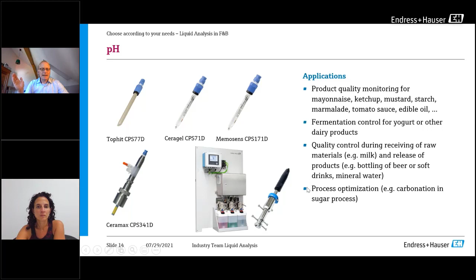Beside that, if you look at the lower left part, we have here an enamel part. To the right is what Floor introduced: a completely fully automated system where you can retract the sensor during the running process, do cleaning, do recalibrations of the sensor, sterilize it, and bring it back into the running process.